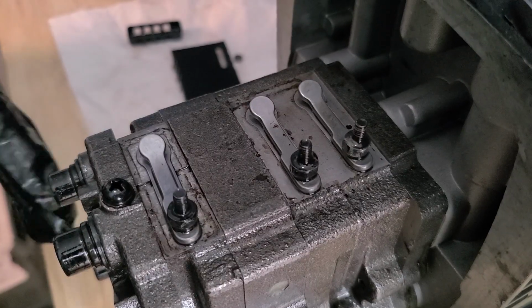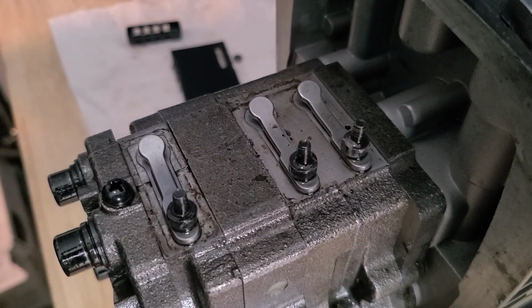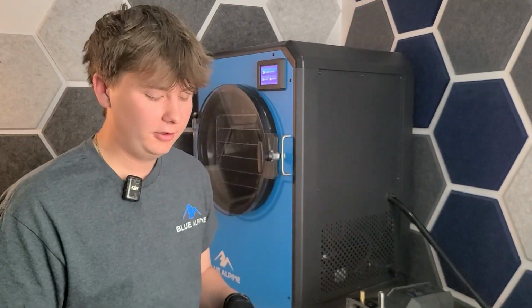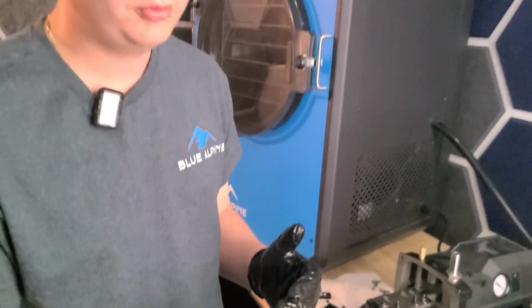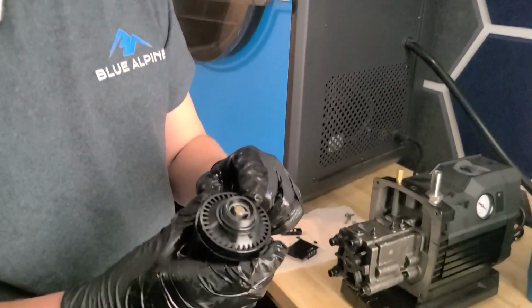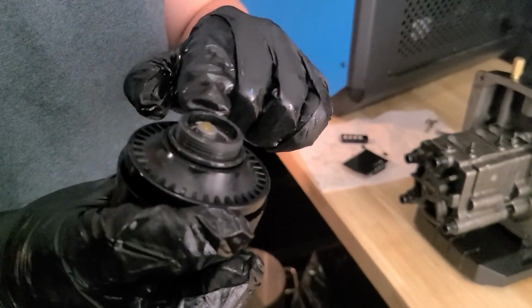The only time you'll need to be sent a new reed valve is if your reed valve is physically cracked or broken. The next thing we're going to look for is the O-rings. There will be 3 O-rings after you take apart the vacuum pump. There's one on the filter. It should be sitting just below the filter like that.